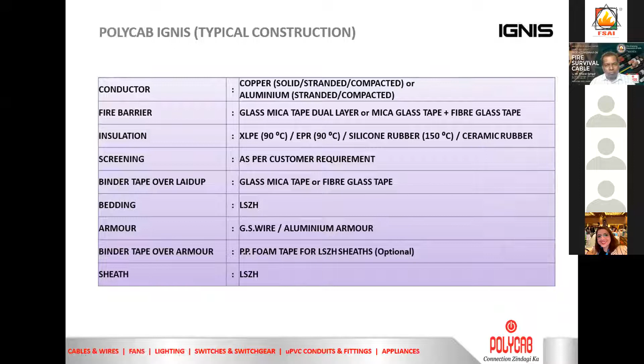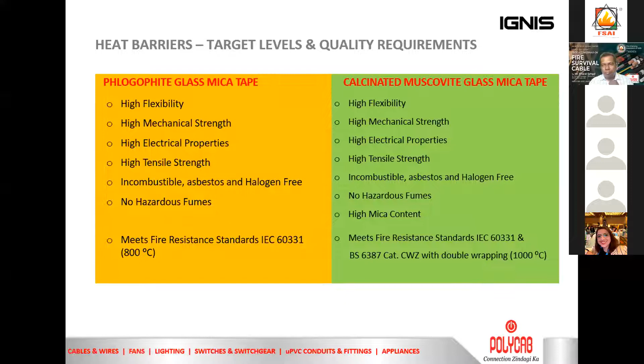One major difference—when I join common industry discussions, there are many voices saying 'sir, we also make FS cables,' but there are many differences: what type of materials are used to produce these cables, and what assured sustainability they have against higher temperatures. If I go to the blue cone of the fire, it crosses 930 degrees, and I cannot assure the cable won't touch the blue cone—so it must be designed around 1000. That's why we use muscovite here, the high-graded mica, so there's always a graded difference in the properties.